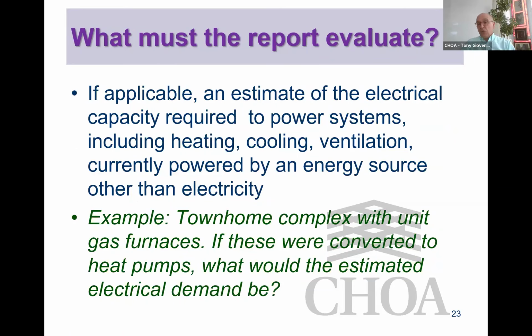So let's talk about evaluating the systems, John, because I think this is where we're getting into some challenges with reports that people are finding confusing. I know. What are the common things that you're seeing? A couple of the common things we're seeing are buildings that have an ambiguity about exactly how much the loading is, looking at the aggregated data, if the wire comes in and goes to the common meter and then all the other meters. Some buildings actually have a single meter that measures the entire thing, and that makes it very clear.